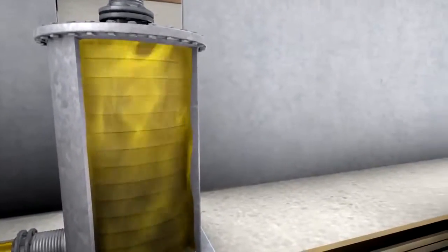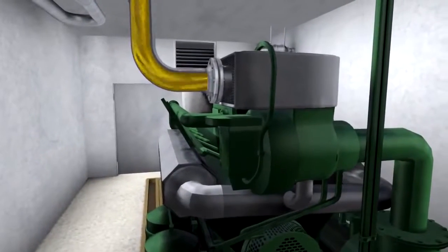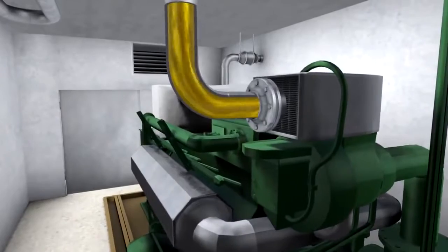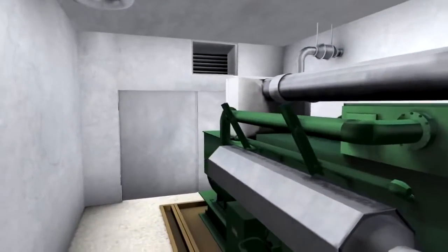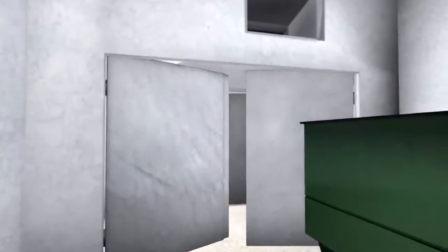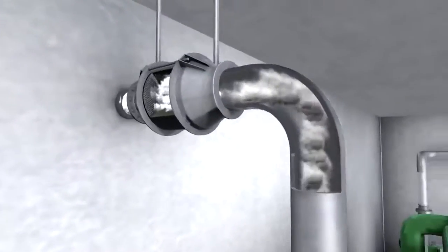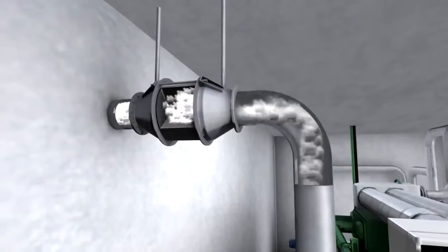The biogas is burned in a combined heat and power unit, which was specifically developed for biogas. The biogas is converted into electricity and heat. In order to minimize noise emission, the CHP is located in a sound insulating cabinet within the plant room. The exhaust arising during the combustion process in the CHP passes through a catalytic converter developed specially for EnviTech plants in order to reduce formaldehyde.